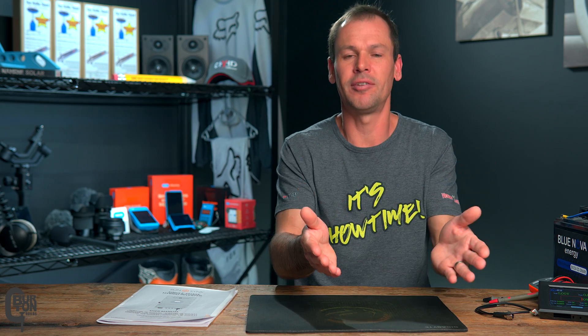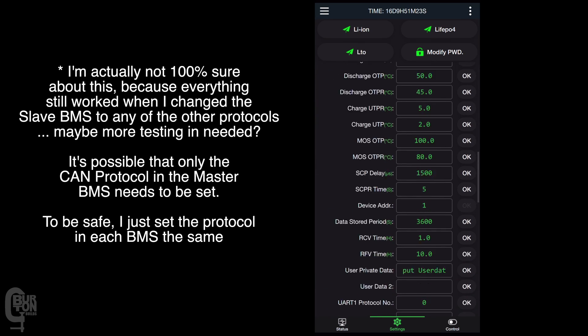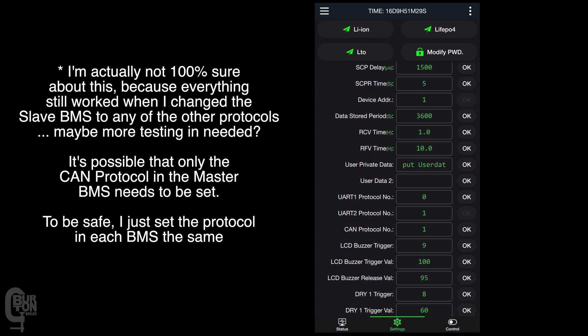Slave battery number one is set to address number one, slave battery number two to address number two, number three to three, number four to four, and so on. Also make sure that the CAN protocol number in each BMS is set to — in our case — 1, Deye low voltage hybrid inverter. This is set in the BMS app basically the same as what we did earlier. If you want to confirm what address has been set on the DIP switches, you can just scroll up and see the device address that has been set.